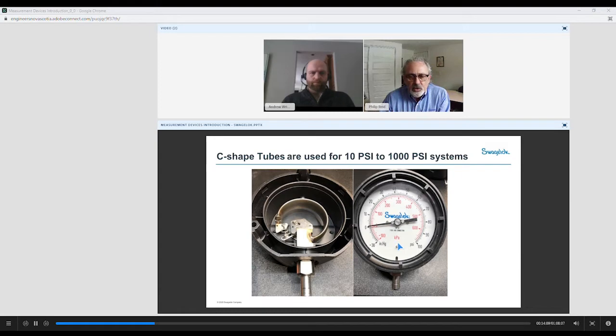Now the markings, as we talked about, are laid out in ASME B40.100 based on the range of the pressure gauge. A few things I'm going to point out about this gauge. This gauge is a compound gauge, and it's a dual scale gauge. This gauge reads positive pressure in kPa and PSI. And in negative pressure, this will read in inches of mercury or negative kPa.